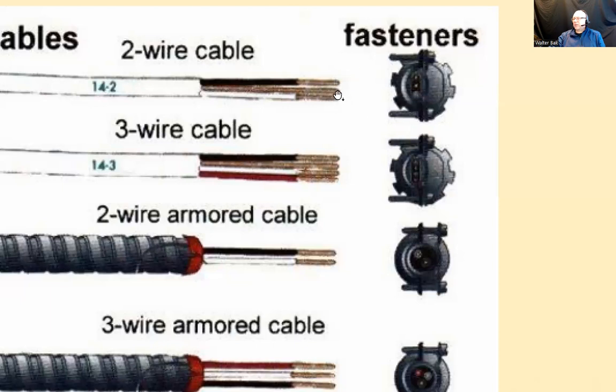If something goes wrong, then the bonding wire should take the hit, not you. What could go wrong? Let's say you have a metal enclosure, a metal box with a receptacle or a switch in it. And for some reason the hot wire gets detached from the screw terminal and touches the metal box. Well, if there were no bonding wire bonding that electrical box to the ground, then because the hot wire touches the metal box, the box becomes hot. If you touch that with your hand while standing firmly on the ground, or touching something else with the other hand that is connected or close to ground, then the current is going to flow from the box to the ground through you, and it's going to take the shortest path. So it could go through your chest, where your heart is.